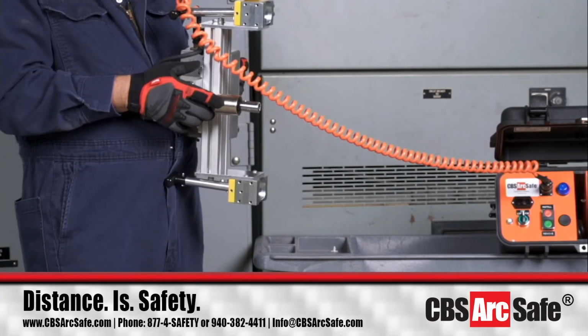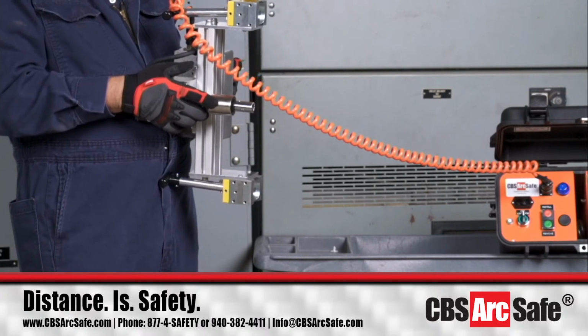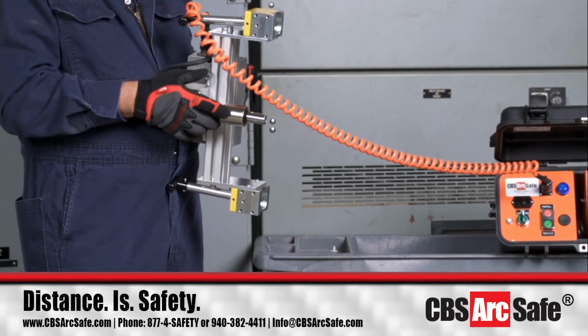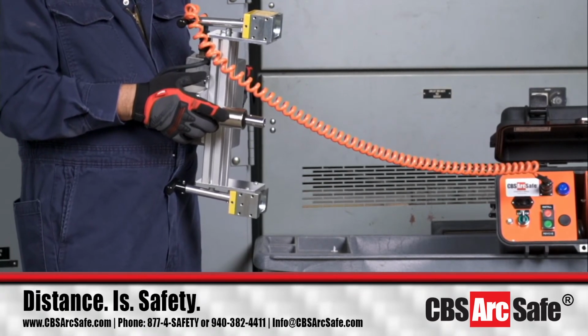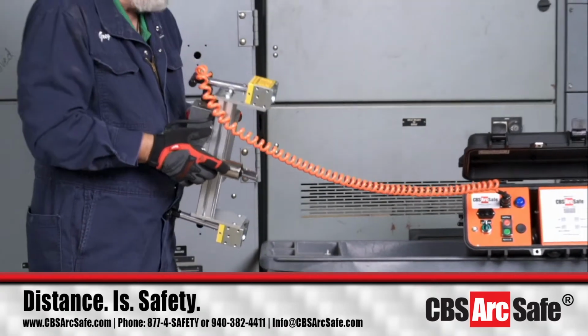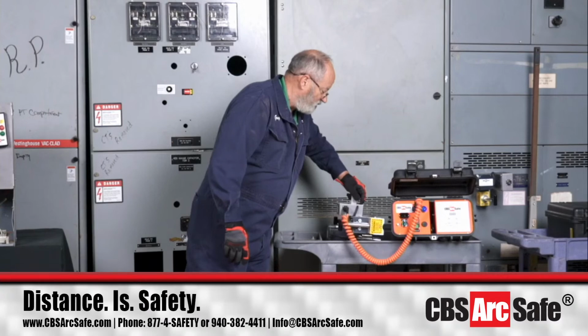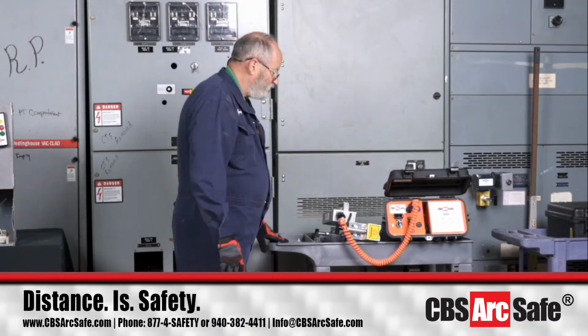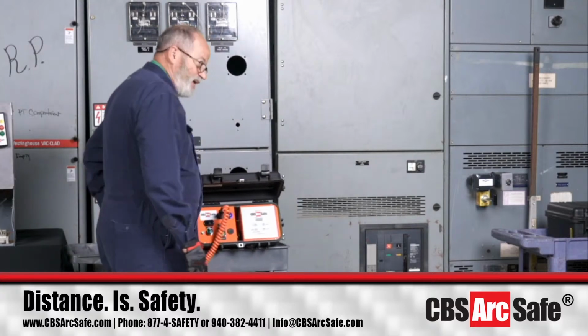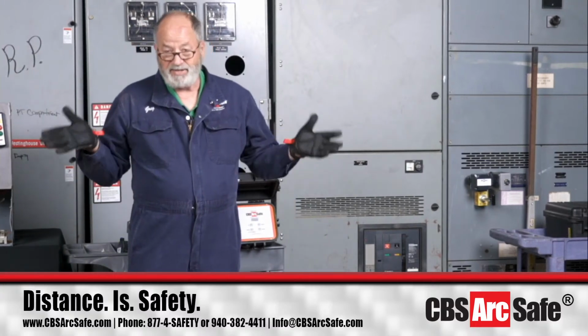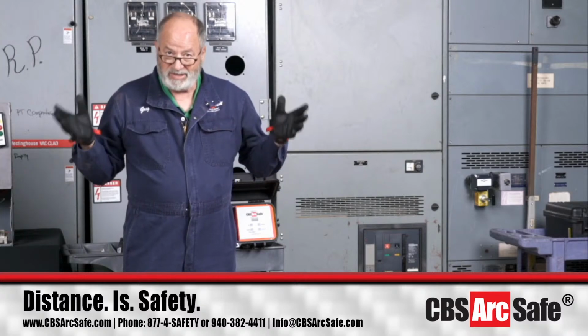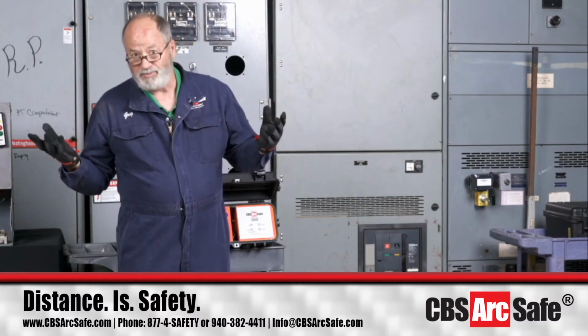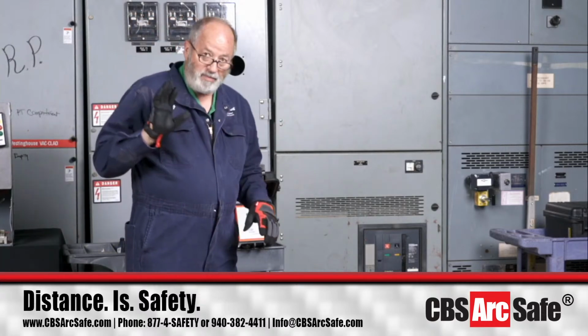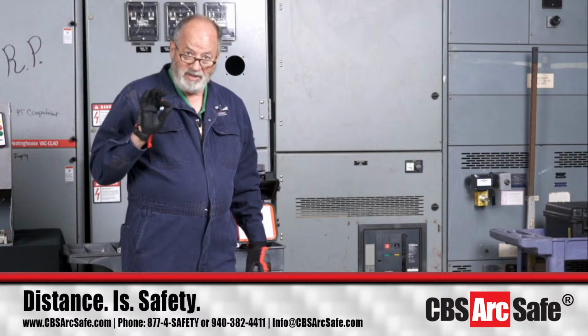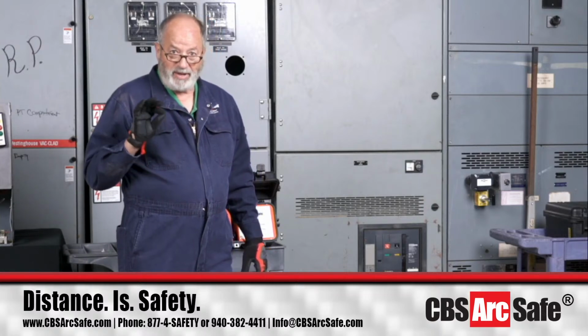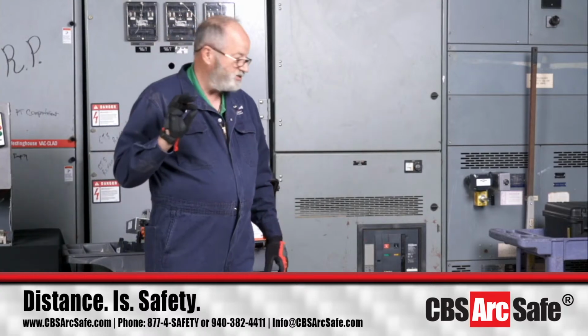If for some reason it's clicking when you first start to rack something in and the system shuts off, it's trying to tell you there's an interference inside of the cubicle. So don't try and force something. The system's trying to tell you something's wrong inside the cubicle. I've actually had customers give me bad breakers and bad cubicles, and I've identified that they have a mechanical issue inside of the cubicle, and they admit that they thought something was wrong. So remote racking does not fix any known deficiencies in your switchgear, but it may help you identify that you need maintenance.